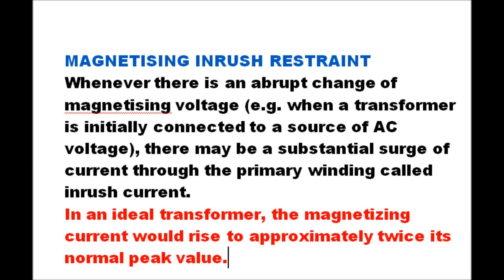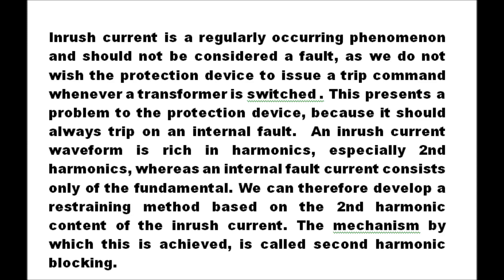Magnetizing inrush restraint: whenever there is an abrupt change of magnetizing voltage — for example, when a transformer is initially connected to an AC voltage source — there may be a substantial surge of inrush current through the primary winding. In an ideal transformer, the magnetizing current would rise to approximately twice its normal peak value. Inrush current is a regularly occurring phenomenon and should not be considered a fault. An inrush current waveform is rich in harmonics, especially the second harmonic, whereas an internal fault current consists of only the fundamental. A restraining method based on the second harmonic content of the inrush current is therefore developed, called second harmonic blocking.